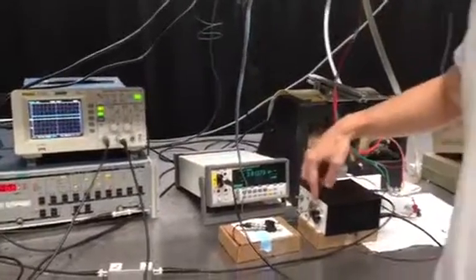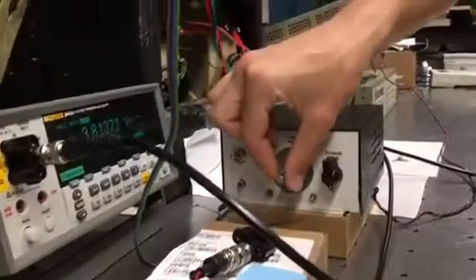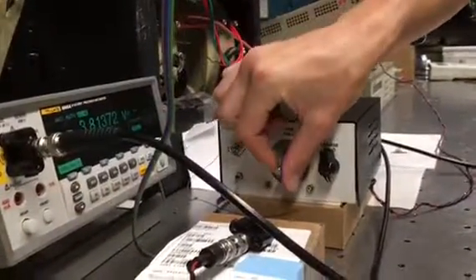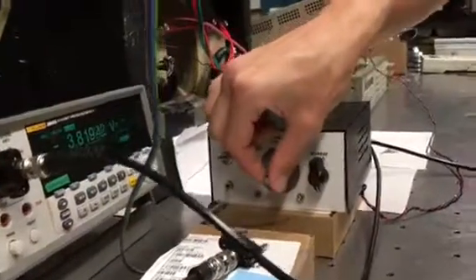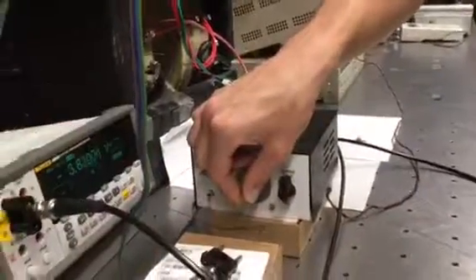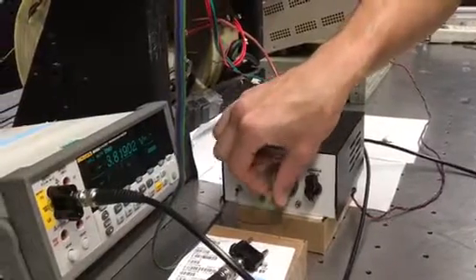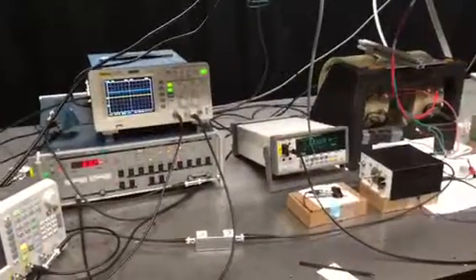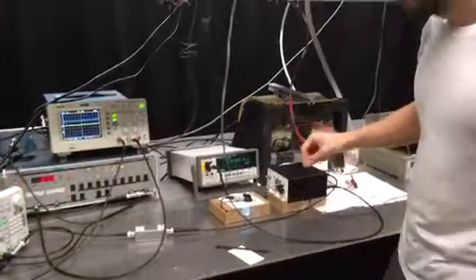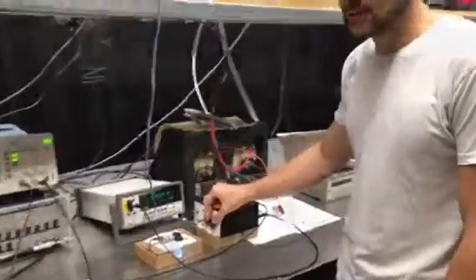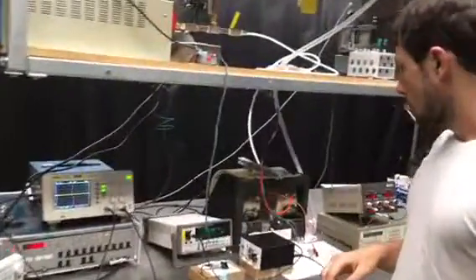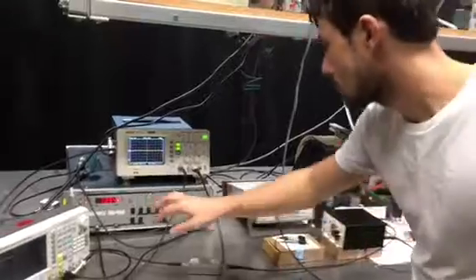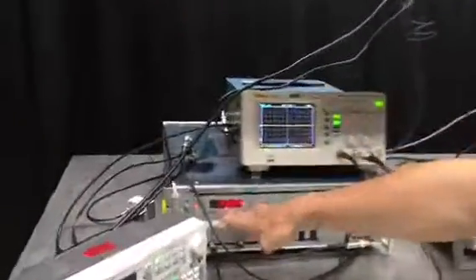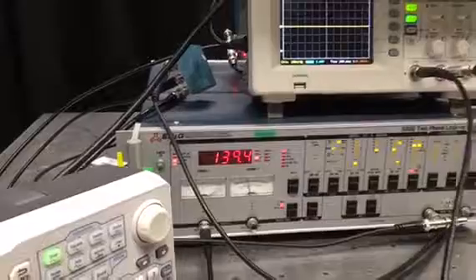So we have the coarse field and the fine field, and this guy can adjust the measured magnetic field by about 7 Gauss, and if you continue rotating it, it will go back the other way. A rather interesting movement in there. So now the search begins. We are ready to start the search, but we can notice that the probe has drifted off into saturation again, just because its parameters have shifted.